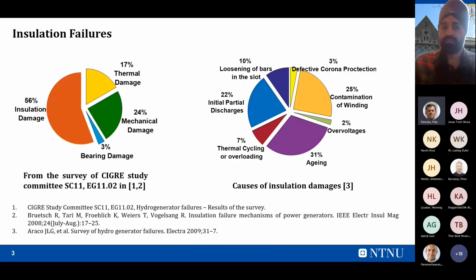The literature also reports various kinds of damage. These figures are taken from around 70 hydropower plant generators, in which, out of 70 failures, 56% of failures are because of insulation damage, 24% mechanical damage, 17% thermal damage, and 3% bearing damage.